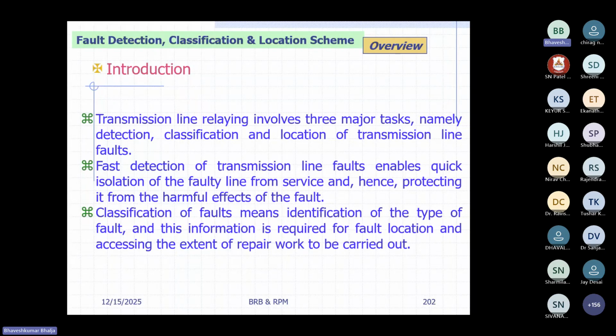That means some severe fault is there, which needs to be cleared by the lineman through utility personnel guidance. Whether we go for a single operation of the recloser or three operations depends on the utility. Usually in our country, or in developed countries also, if you have installed auto reclosers at transmission level, then only a single shot is to be attempted. So whenever there is a fault, the breaker becomes open, and you reclose after 300 milliseconds. If there is still a fault, then it is identified as a permanent fault and the breaker pole remains open. So this is to be attempted by the utility at transmission level.